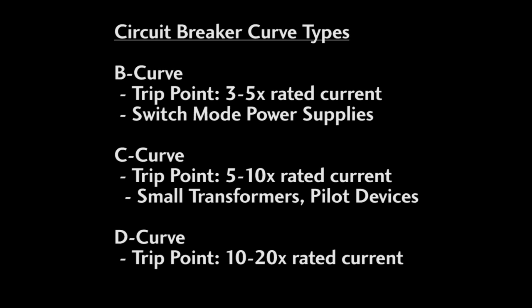The D type curve trips at 10 to 20 times the rated current. These are used for transformers or high inductive loads like motors that need time to get past the high inrush current without the circuit breaker tripping.